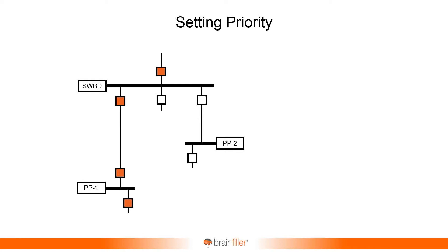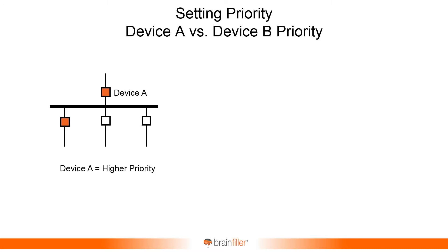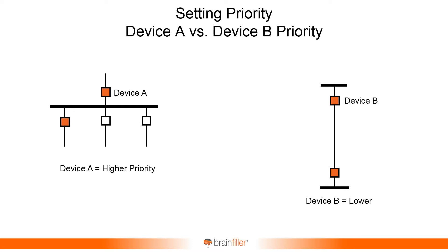So how do you determine the priorities of devices? Let's say we have four devices in series: a main, a feeder, another main, and another feeder. You have to look at priority in terms of what I define as an A priority and a B priority. A is the highest priority — it means you have a device such as a main feeding multiple feeders. If that main trips, you lose more than one circuit, resulting in a wider outage.